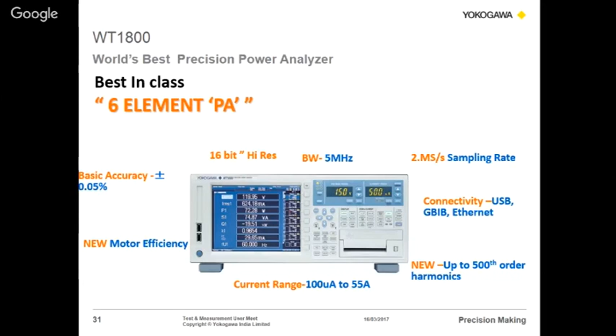So you can see the 6 elements. Each element is a channel. These are all the voltage inputs, and these two are the current inputs. So voltage and current. If you are connecting through CTs or Hall effect sensors, this BNC connector will be used. Normally Hall effect sensors give a voltage output, for example 1 millivolt per ampere or 10 millivolts per ampere. So the voltage output can be connected through this BNC.